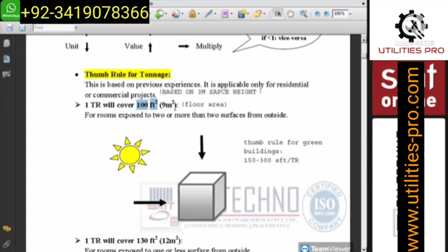Okay. So this is simple. As per the thumb rule, 1 TR will cover 100 square feet of floor area. With the height, we are considering the standard 3 meter. That is nothing but 9 point something square meter, rounded off to 9 square meter. Okay. But we have a condition. This 1 TR will cover 100 square feet if you have exposure on more than 2 sides.